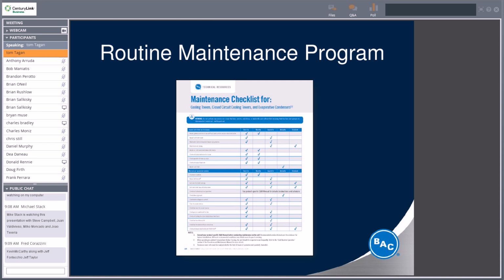Check the operation of the makeup valve. We have two types. We have a float-operated makeup, which is kind of the standard. We also have an electric water level control. The float-operated makeup is your typical float and ball valve, similar to a toilet makeup. The electric water level control is a series of probes that senses the water. Typically, you have high and low level alarms along with that. So you want to check the operation to make sure you're not overflowing or pulling air into your system by too low of a level.